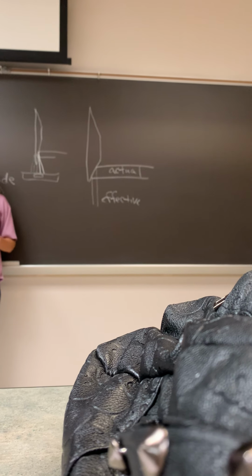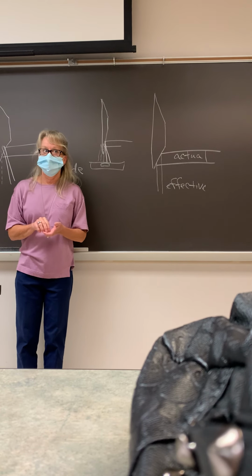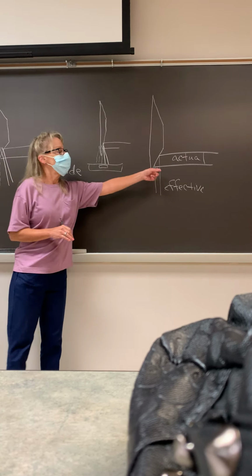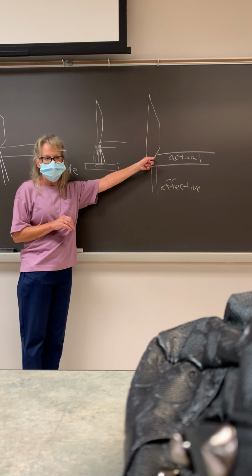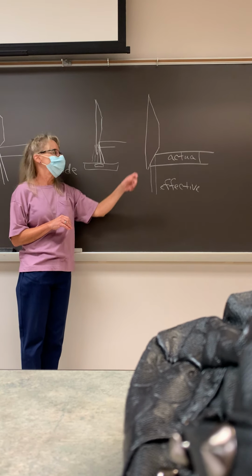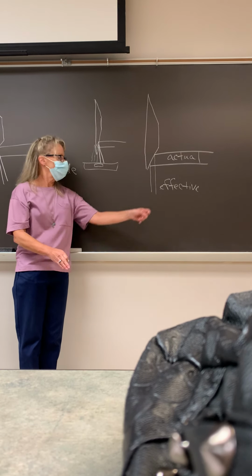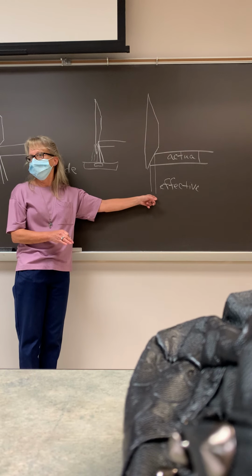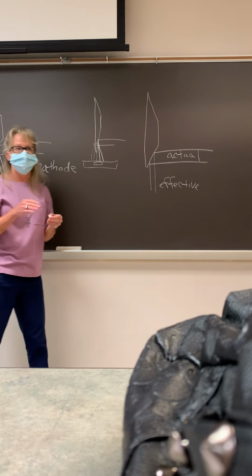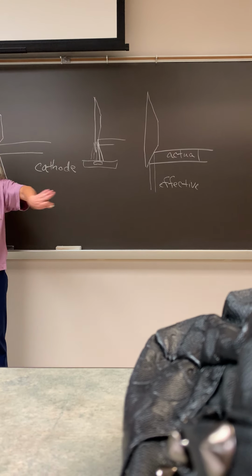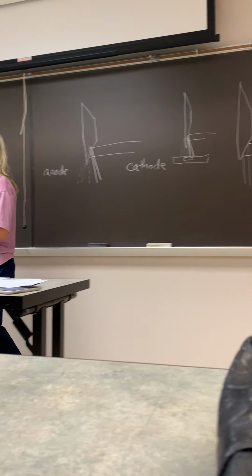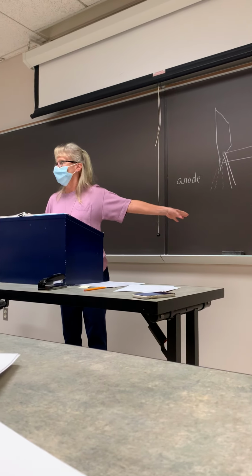Okay, that's why they say if you're doing extremities, if you can, pick the small focal spot versus the large. Okay. All right, so the actual focal spot is the actual area where the electrons hit. The effective focal spot is the effect of that bevel. Always makes it smaller, which is what you want, okay, for better spatial resolution. The more spreading you get, the more blur. Okay. All right. We good with this?